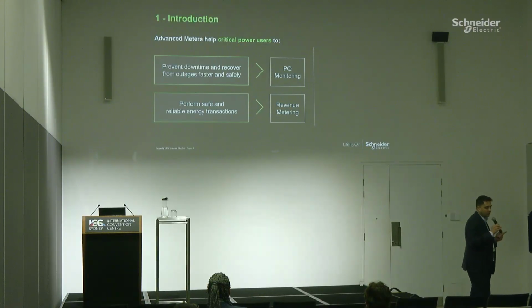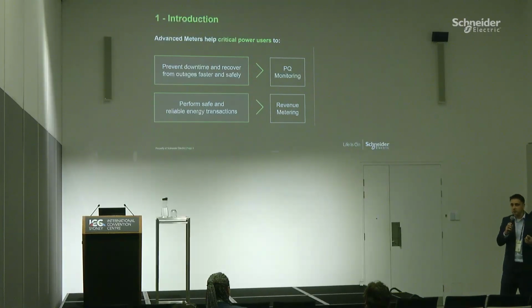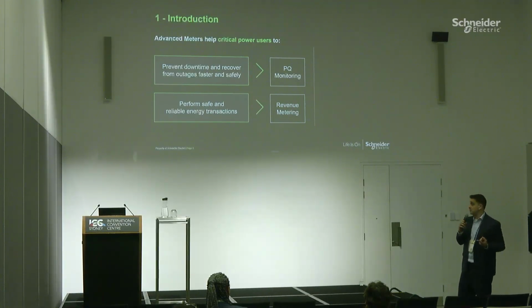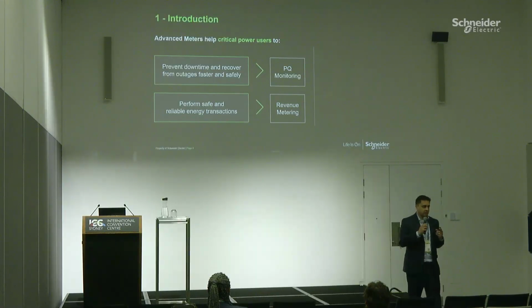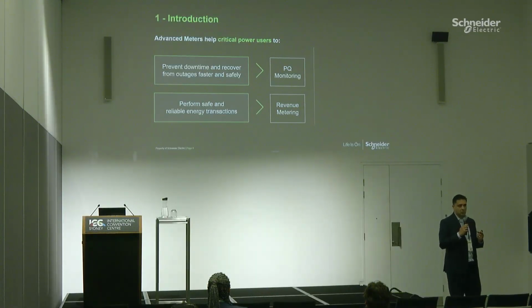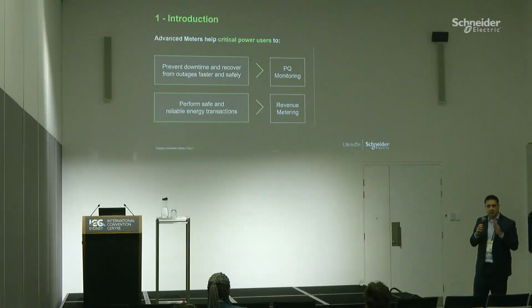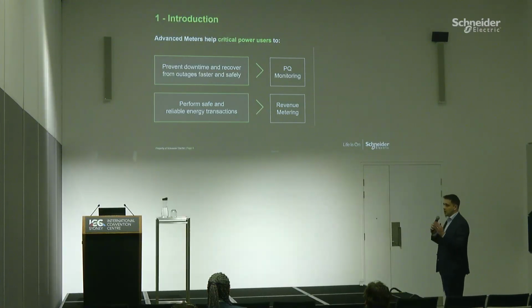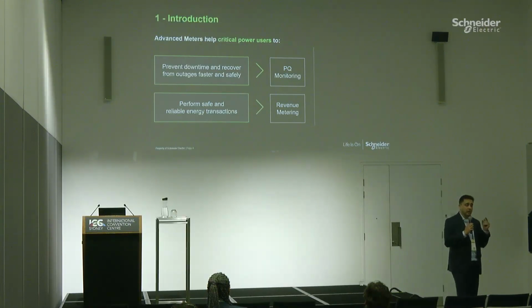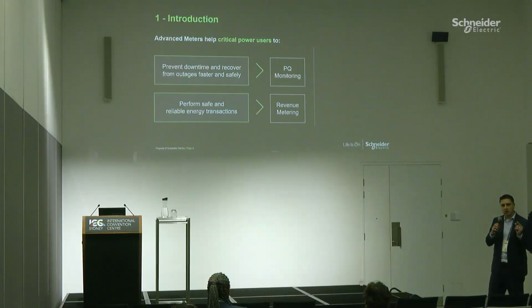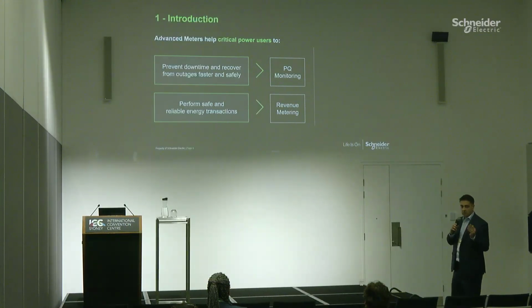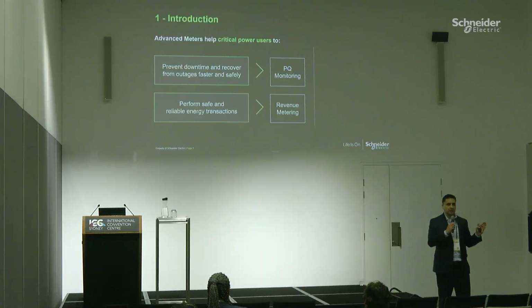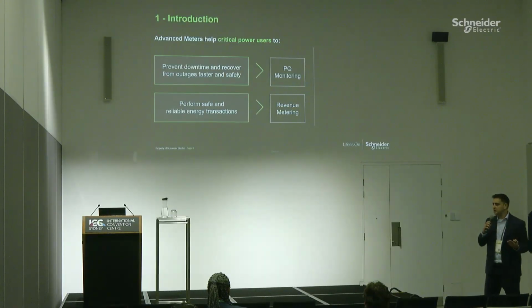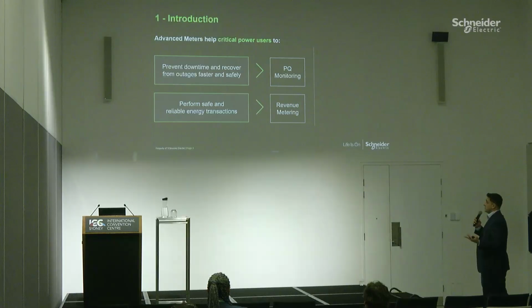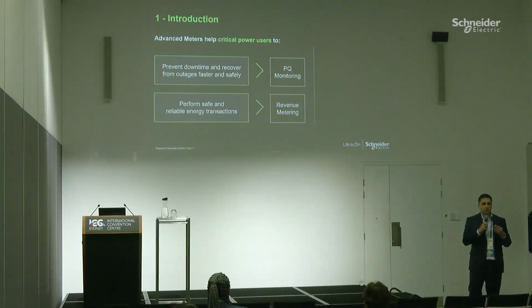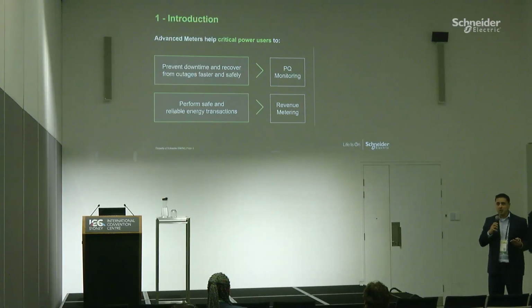The second pretty important characteristic is the ability to measure different power quality events. That comes coupled with the ability of the devices to sample the voltage and current signals quite fast, so you can detect those power quality events, which a lot of times are quite fast. You need fast sampling of voltage and current to detect those power quality events. And the third characteristic is the ability to store those power quality events.